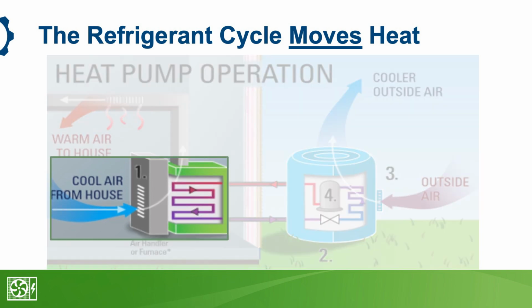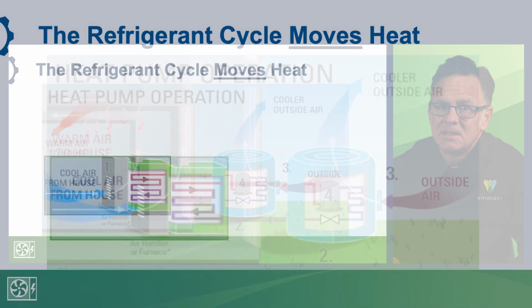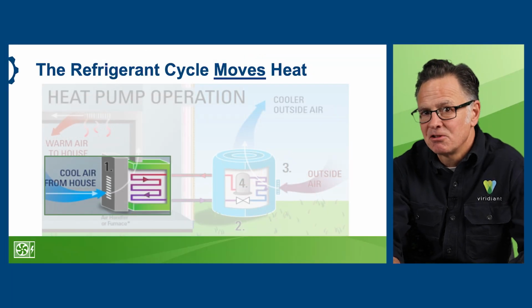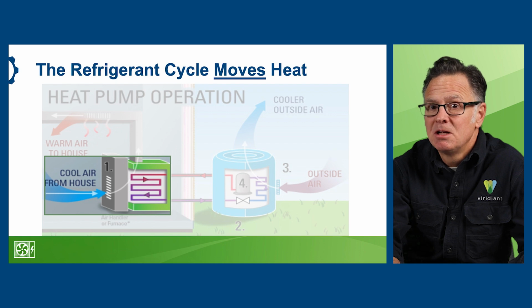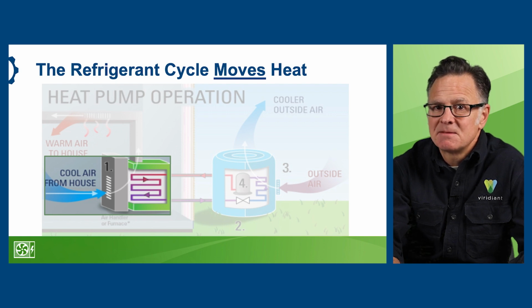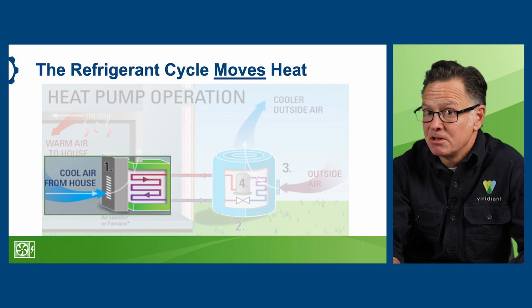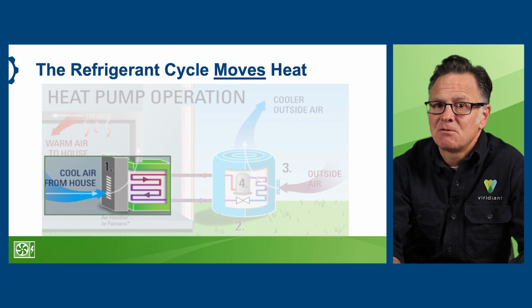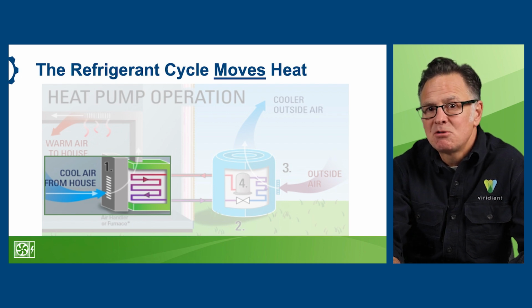In the winter, cooler air from the home enters the air handler via the return plenum to be heated. Instead of passing through a heat exchanger warmed by burning fuel, the passing air is heated as it passes over the same radiator coil used to cool the home in the summer. In the heating season, that coil contains high temperature, high pressure gas, a refrigerant. As the cooler air passes over the coil, it takes on the heat of the refrigerant. The gas then cools and condenses into a liquid.